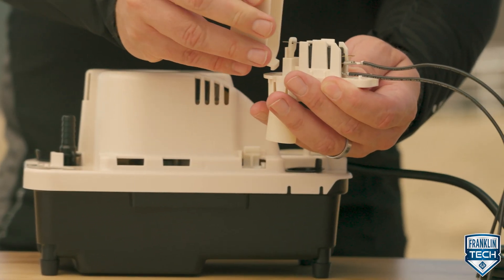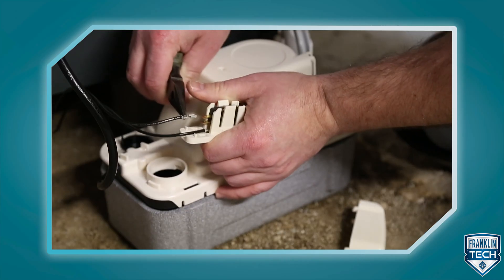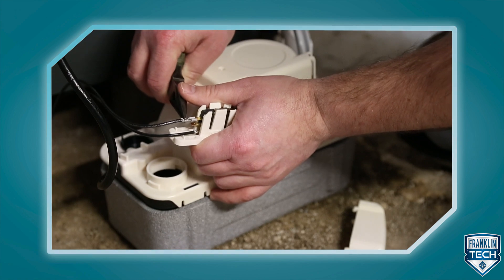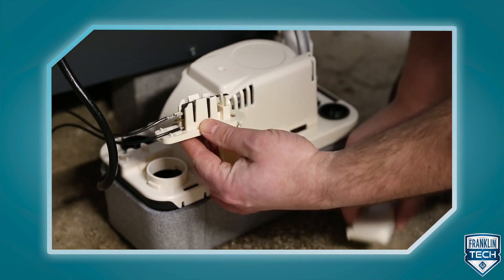If the switch is wired to the NC terminal, the air handling device should shut down when the float is raised. If the switch is wired to the NO terminal, the external components such as an alarm or relay should activate when the float is raised.